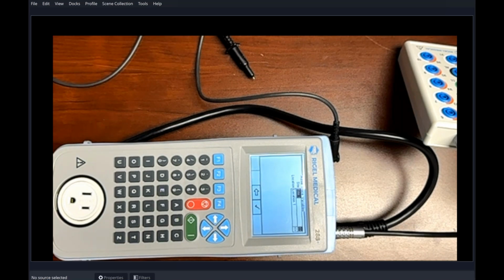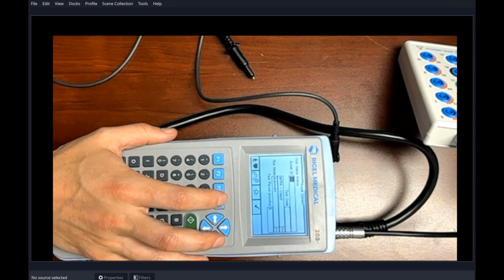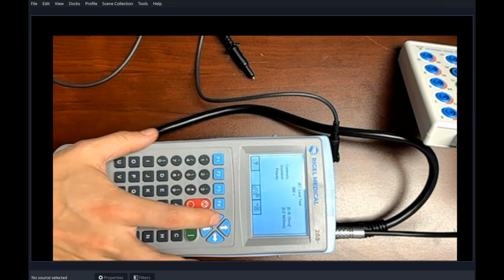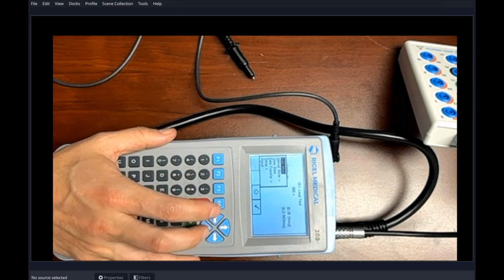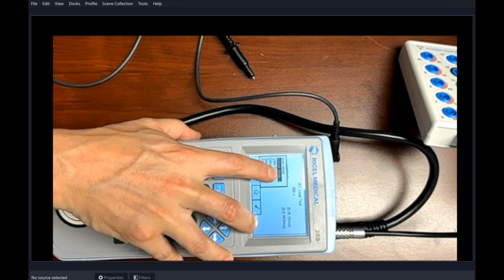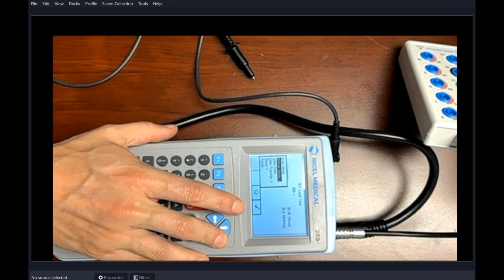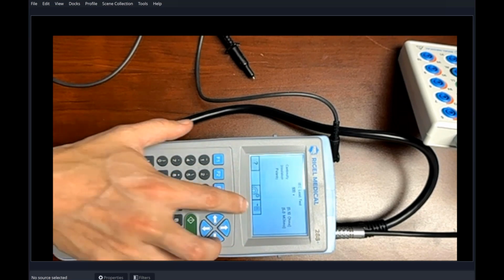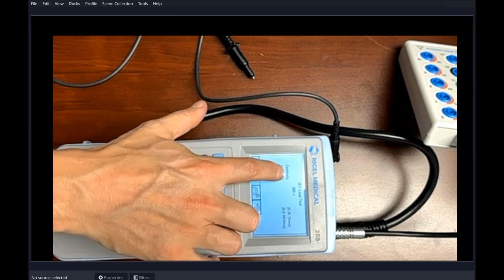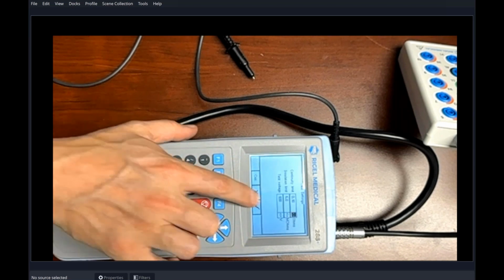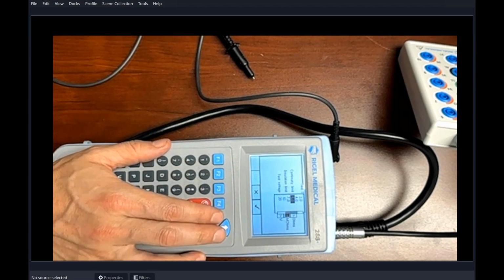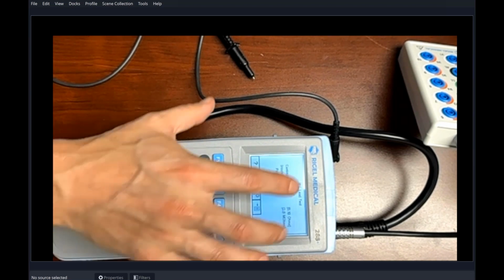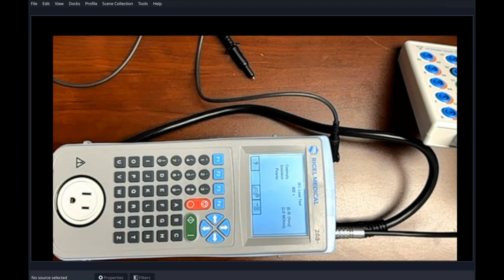I'll go back to the IEC test. Sorry about that. So that IEC test I was explaining was in the manual mode, and at the bottom here, the results can be changed on here. So F3, test limits, and that's where you can go in and check your IEC lead to ensure that it's not the device that's failing, but the lead that you're testing. So you can always go back and verify all your test leads, not just the devices themselves.